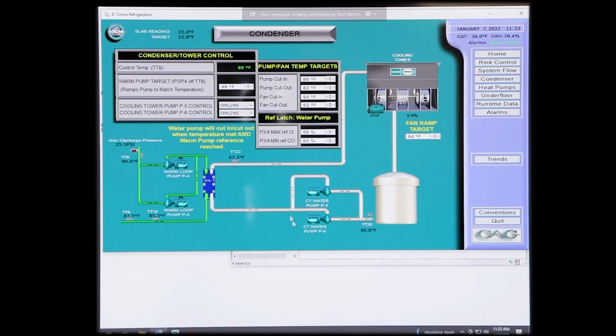Your P5, P6 pumps here, your water temperature, your water tank, your fan ramp target is 94 degrees. That temperature is being read off TT22 right here. So literally, as you see, this is 67. We will not start ramping this fan at minimum speed until 94 degrees. So that water is toasting warm. If you're feeling a chilly day, go climb into the tank. You'll get nice and warm really quick. Any questions here? Okay. Again, just another rereading of slab temperature reading up here in the target.